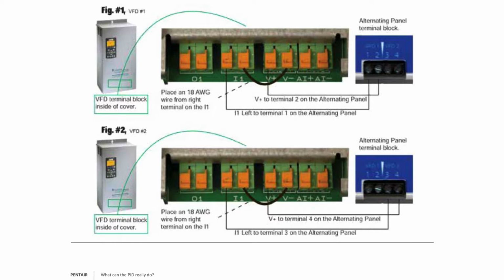Now, the second VFD drive, you would then wire it the same way, but programming it would be different. So for example, this is going to be a run command. So basically what we're going to tell it is, when we have these wired up, we're going to go into our main menu, and to get in there, remember you might have to put in your password again. So put your password in, enter, then go into main menu, scroll down to input, output, I/O, enter, and then scroll down to say input 1 or input 2, and we're going to make that look at a different external input, a pressure point, a different pressure setting.